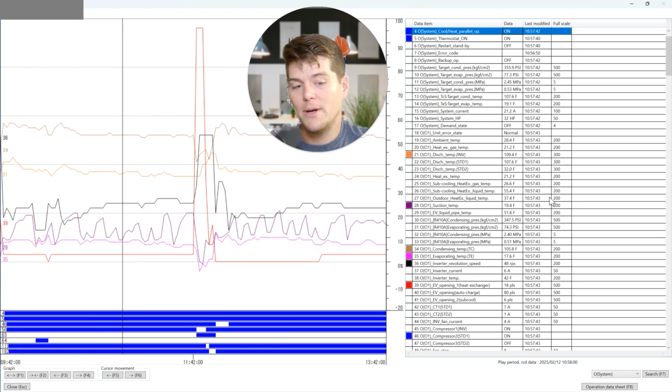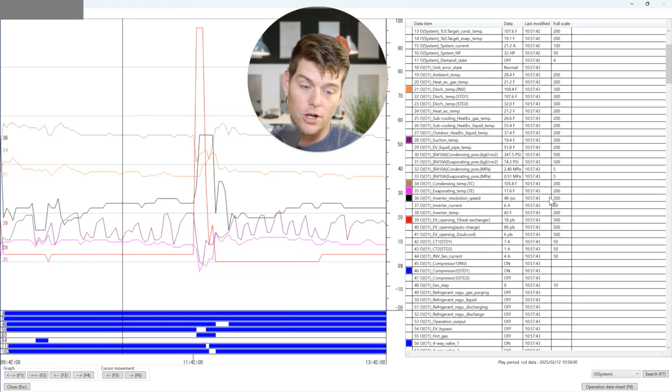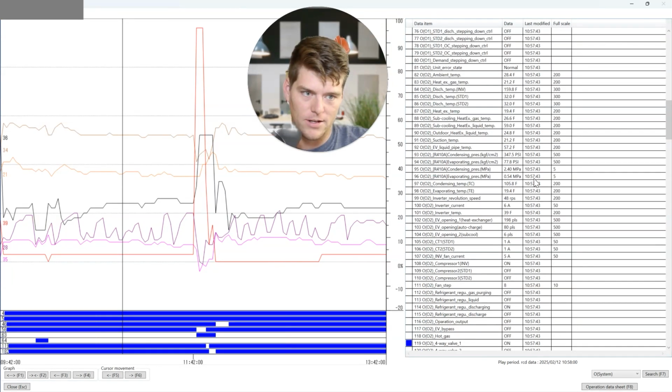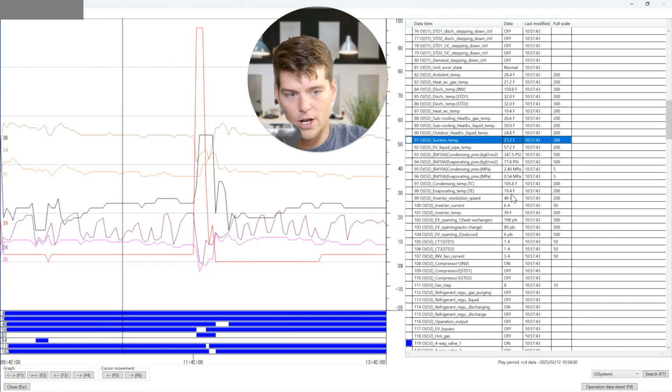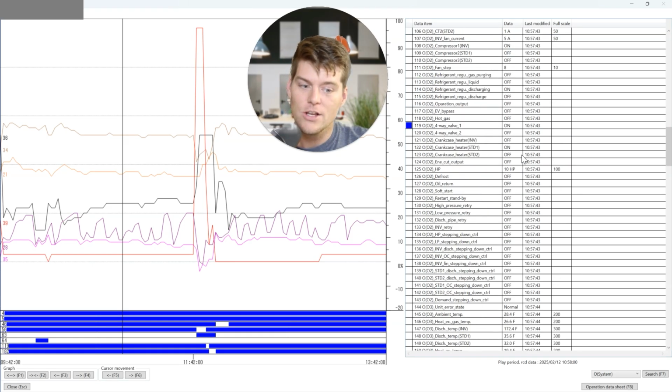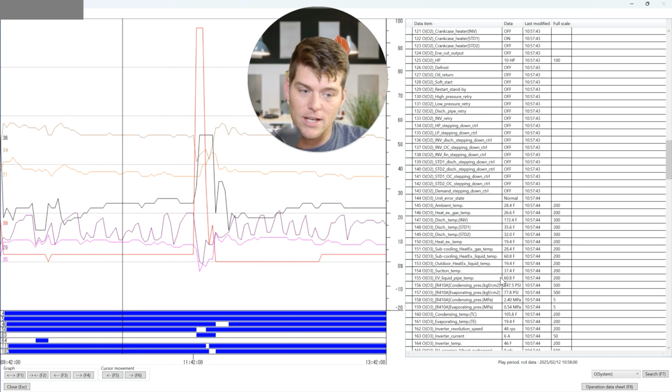If liquid refrigerant was coming down my suction line, where's it going to go? It's going to go to all 3 modules. Now, it's going to hit my master module first. However, my sub-modules would also be affected. And is that the case? Suction temp is 21. And here we have 19. It is the case. So I am also getting liquid refrigerant from inside.